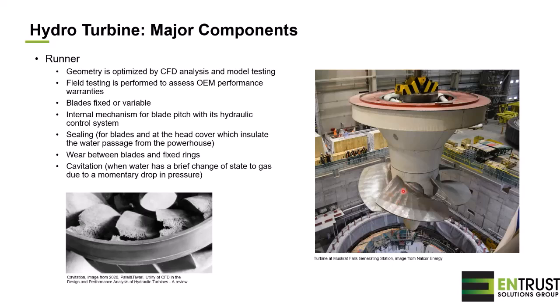And what is important, especially for Francis turbines, since there's a significant amount of pressure drop, is cavitation. And here's an example of cavitation damage on a runner. Cavitation is simply a brief change of state from liquid water to gas due to a drop in pressure. And by doing this change of state, it will pull the material out of the blade. So eventually we'll find holes in the blades.